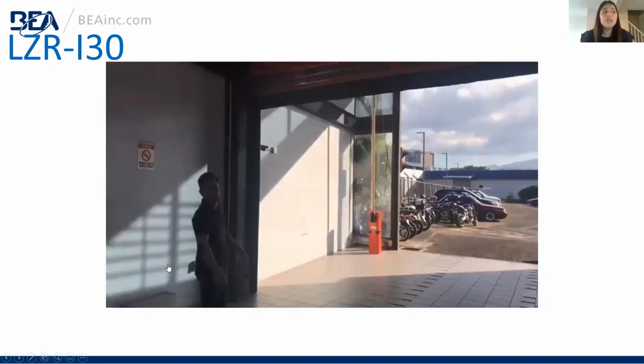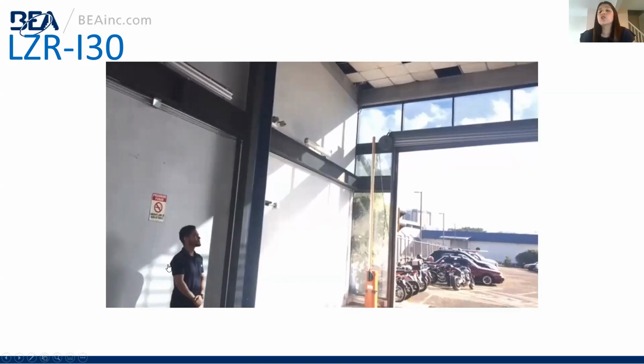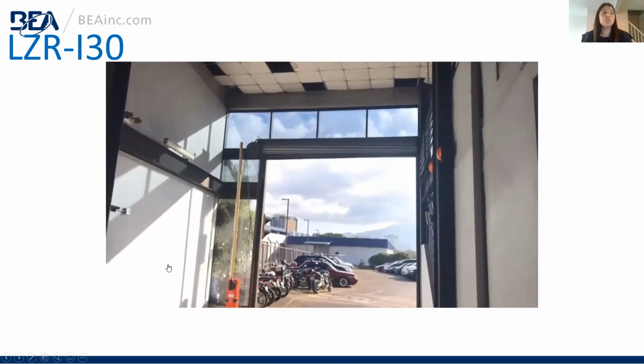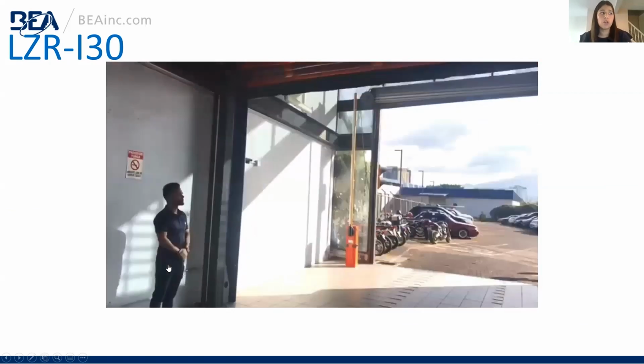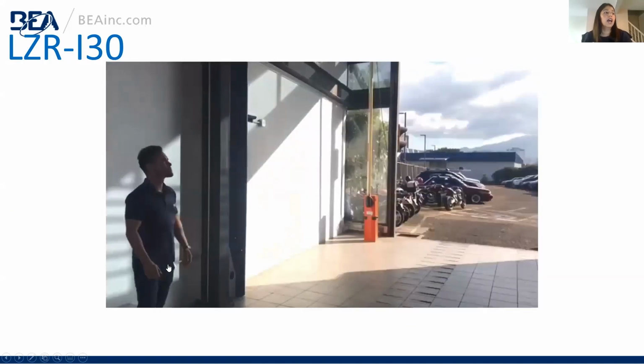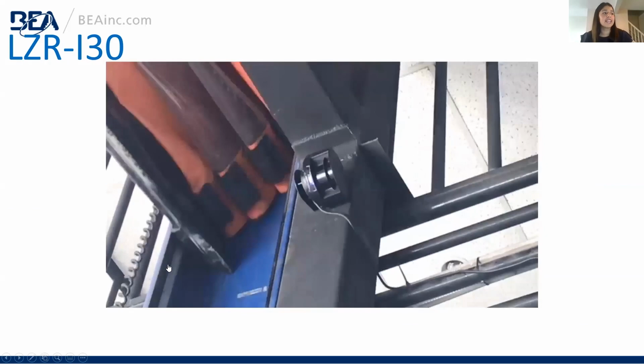As the sensor found him, the door went up. So we use one of the relays for that. Now, obviously, we also want to protect the door, so the other relay will be designed for the full coverage of the door, and you just want safety, meaning if the door is moving, you don't want it to close on someone or something, and that's what it's doing. So you can see how that is working, and I think that gives a really good representation of what the sensor can do, and you can see there how the sensor is detecting him.